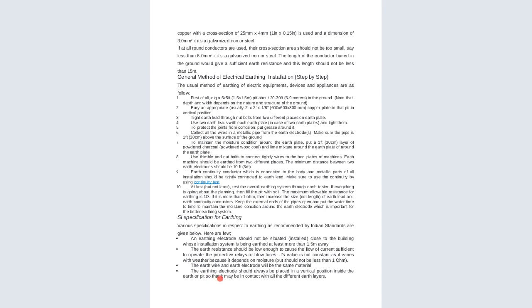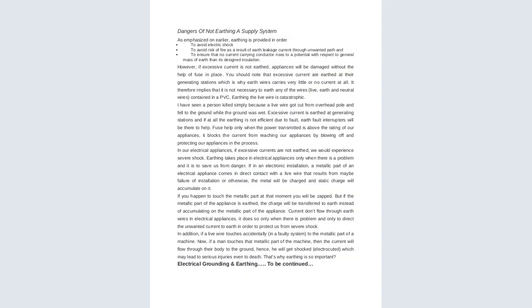Another one is that the earth wire and the earth electrode should be of the same material. And then the earthing electrode should always be placed in a vertical position inside the pit, so that it may be in contact with all the different layers.